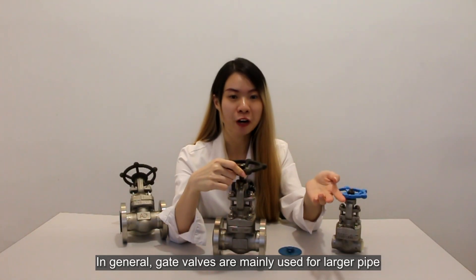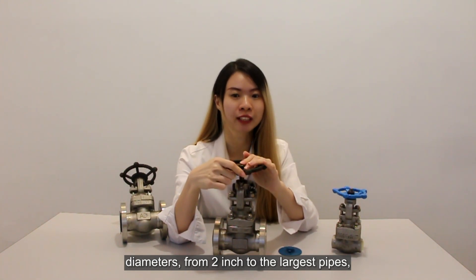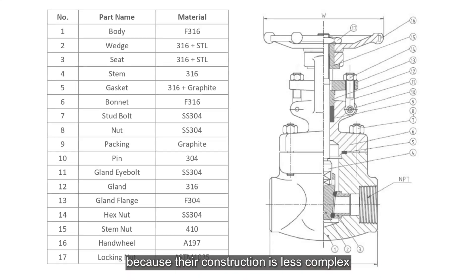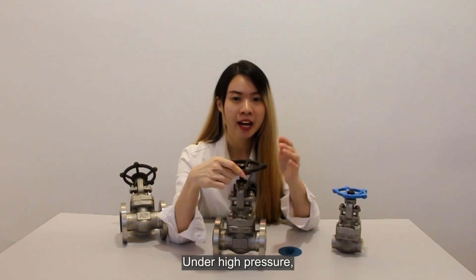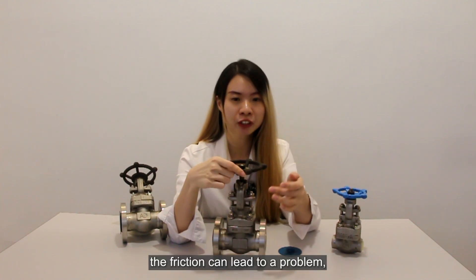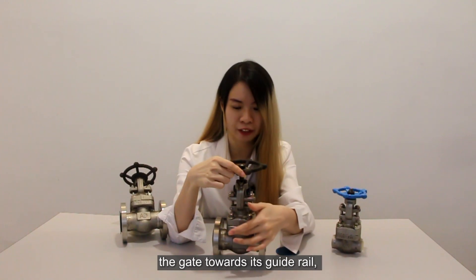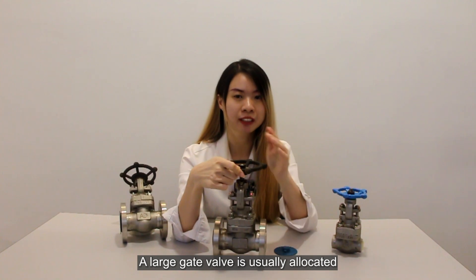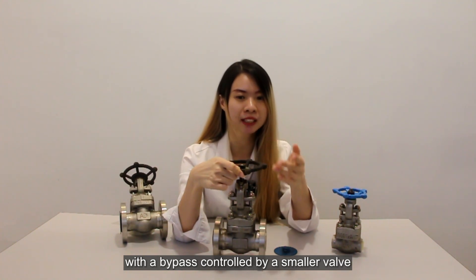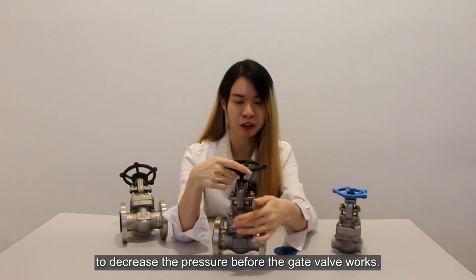In general, gate valves are mainly used for pipe diameters from 2 inches up to the largest pipe sizes. This is because their construction is less complex than other large-size valves. Under high pressure, friction can lead to problems. As the pressure of the medium pushes the gate valve toward its guide rail, it results in difficulty operating the valve. A large gate valve is usually fitted with a bypass controlled by a smaller valve to decrease the pressure before the gate valve operates.